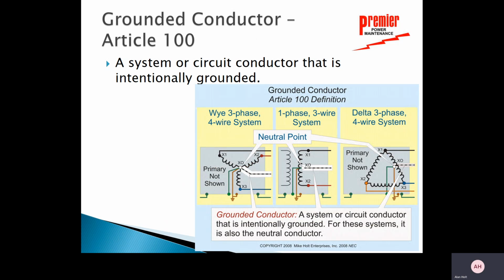Now, Article 100 and Section 250 talk about the grounded conductor, okay? This is a system or circuit conductor. It is a current carrying conductor that is intentionally grounded. So if I look at these systems, a three-phase, four-wire system, a Y system, I've got the neutral point right there. Guess what? It's intentionally grounded, okay? I'm not showing the primary of the transformer. If I look at the single-phase, three-wire system, by definition, right here's the neutral conductor. It's grounded.